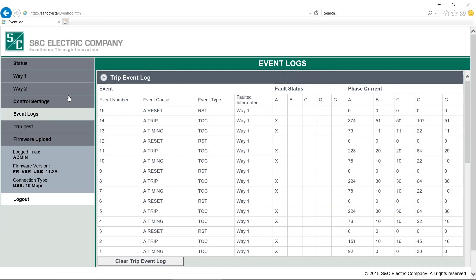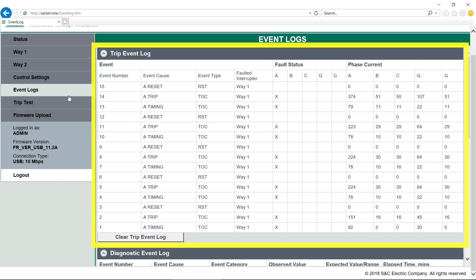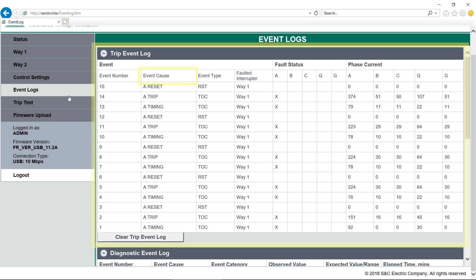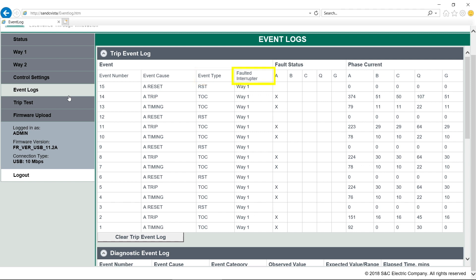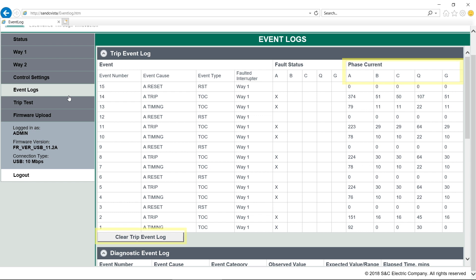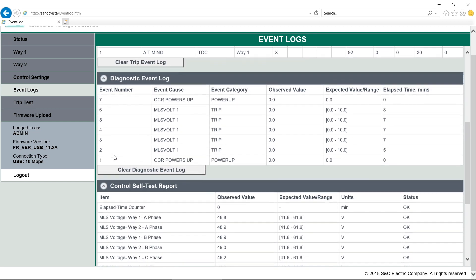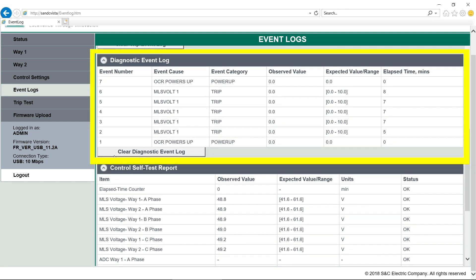When we click on the Event Logs tab here below Control Settings, we'll see the last 64 events recorded by the trip event log. The trip event log will record event messages in the order the event occurs, with the most recent event on top. Trip events will remain recorded even if the control loses power and will only be removed if more than 64 events are recorded, the oldest event will be overwritten, or if the log is cleared manually. The Event Cause column will show the cause of the event that occurred, and the Event Type column will display which element initiated the event. The interrupter that responded to the event will be displayed under Faulted Interrupter, and the Time Overcurrent Phase, or element, will show up in the Fault Status column. The phase current at the time of the event is also shown. We can clear the event log by clicking here.